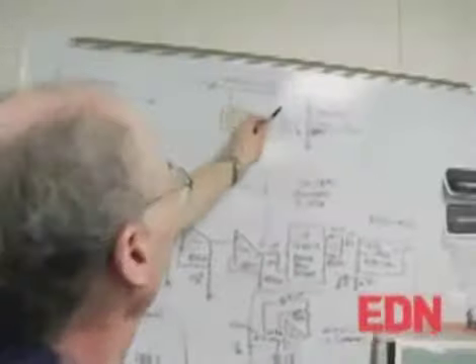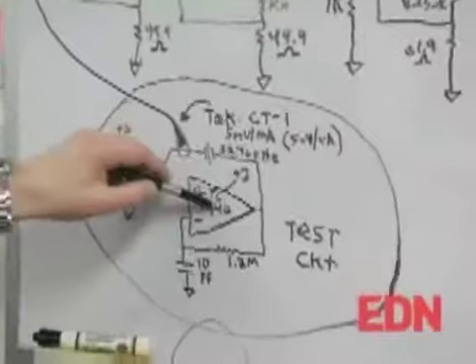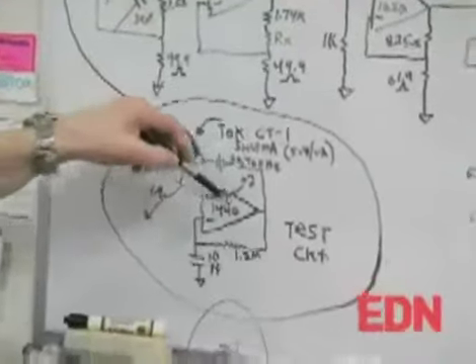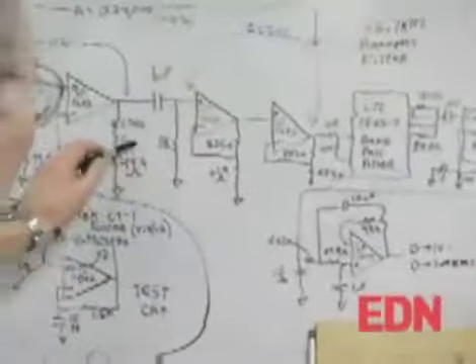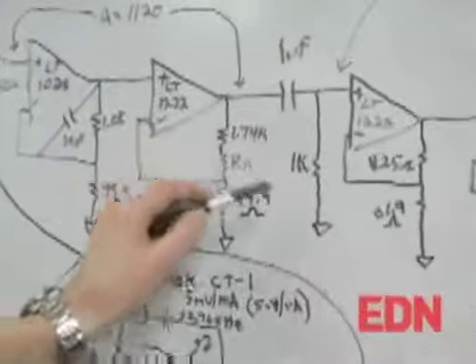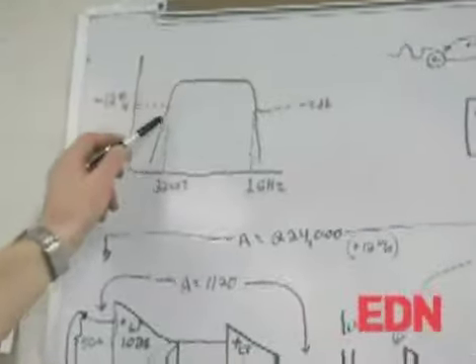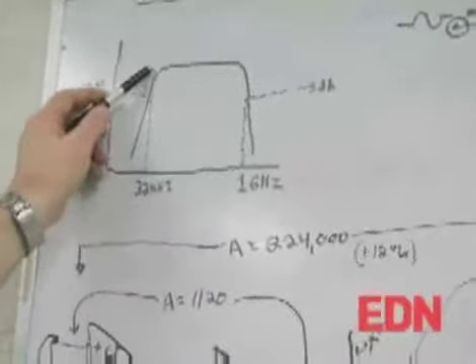The way to make sure we get it is to once again come back here, stick our tenth volt through 100k through the CT1, turn this off. So now we're sticking a known current through here of a microamp and adjust the gain at this stage for exactly this scale factor. And again, we can get away with that because we're only running at one frequency. There's no harmonic that the current probe is subjected to, so I can get away with this gain boost because I'm so narrow banded.